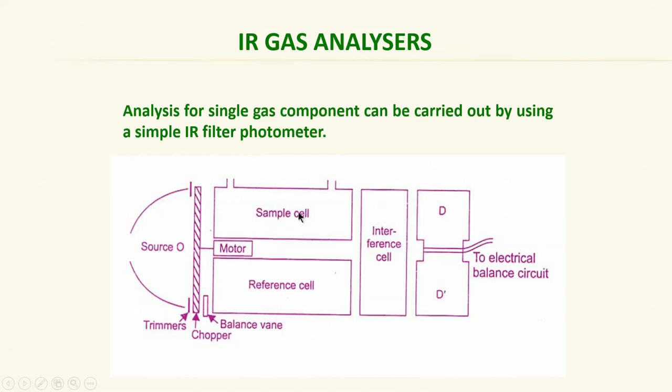I have a sample cell, this may be about 10 centimeters, 10 to 20 depending upon the analyzer sensitivity we need. I have one sample cell and one reference cell. Here I have an interference cell which also contains some of the gases that we want to eliminate that are present along with the sample. But in the interference cell there is no actual sample. These are other gases that are present in both the sample cell and interference cell.